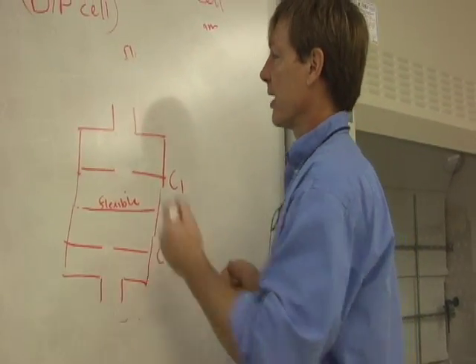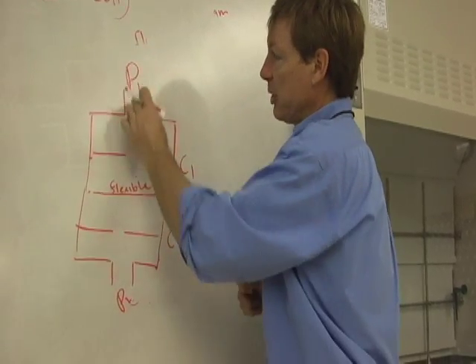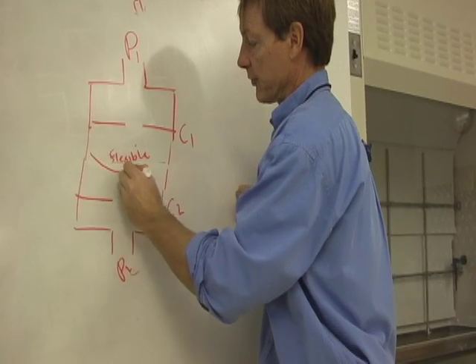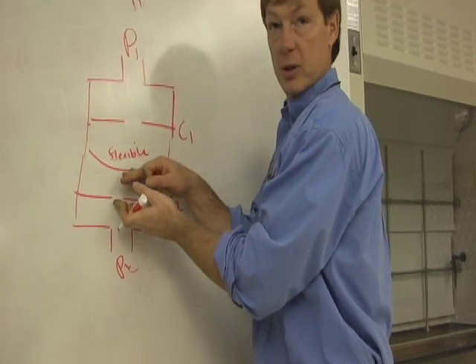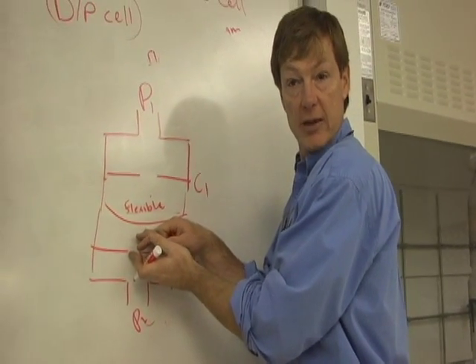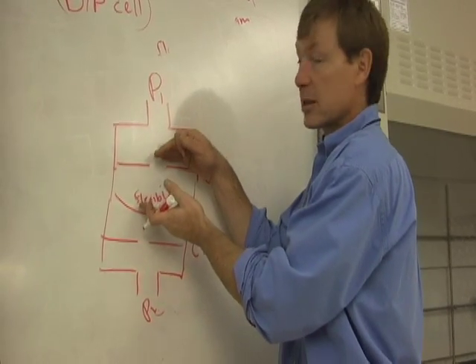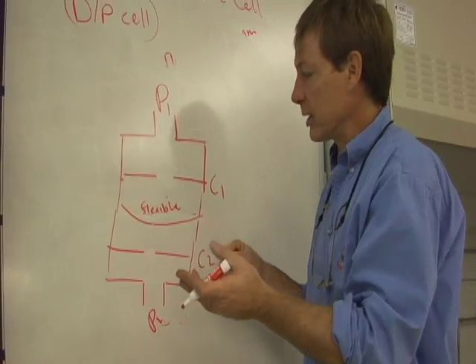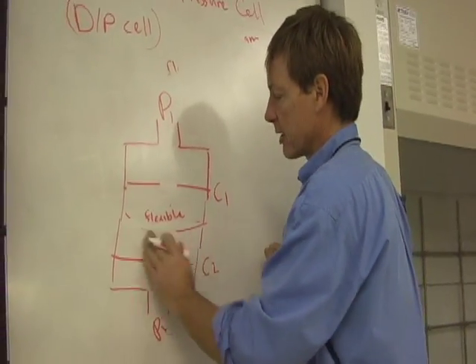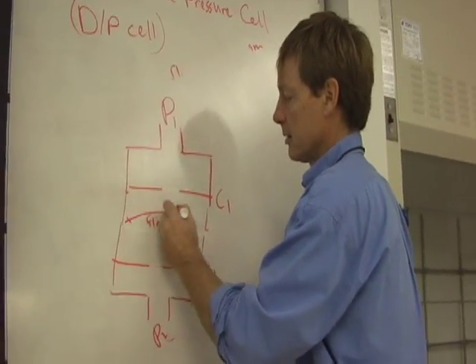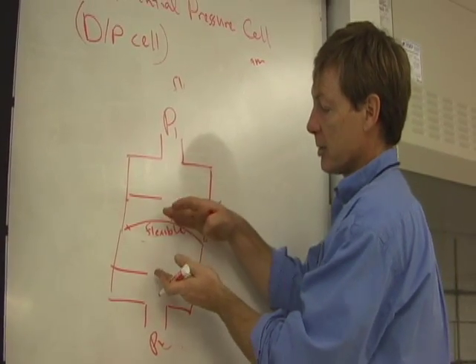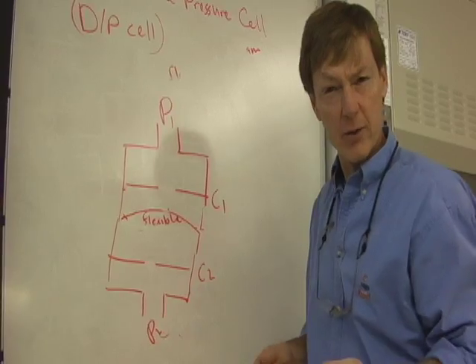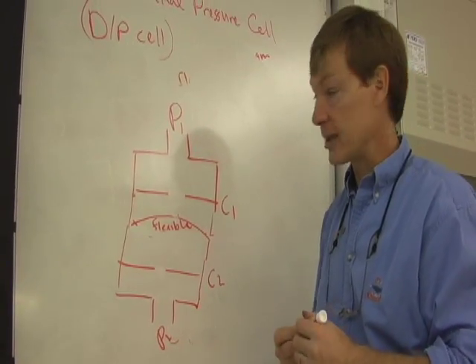So if P1 is higher than P2, this flexible diaphragm is going to flex this way, and the distance between these plates is going to go down, and so the capacitance is going to increase on this side. So you can compare them and you get very accurate readings. If P2 is greater than P1, it's going to flex this way. It's an exaggeration. But now I've got less capacitance here, more capacitance here. And I can compare those capacitances and get a pretty good idea of how it works.